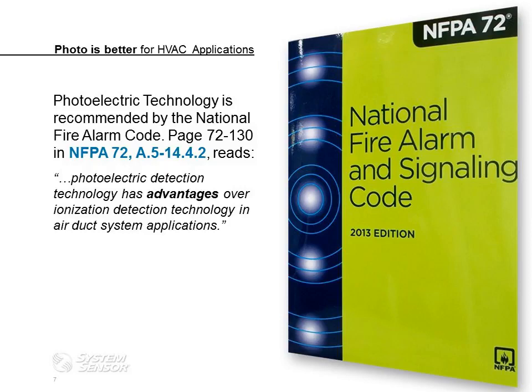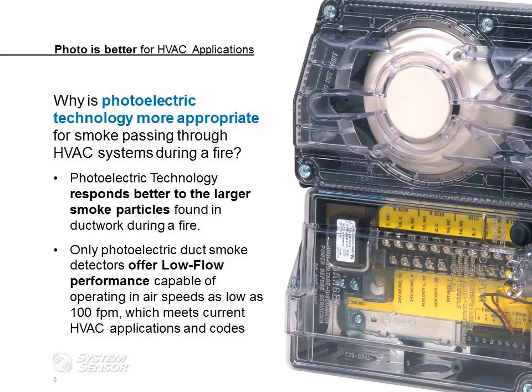NFPA 72 recommends the use of photoelectric detectors for HVAC applications. Photoelectric detection technology has advantages over ionization detection technology in air duct system applications. So what are those differences, and why is it appropriate to use photoelectric versus an ionization detector? Photoelectric technology responds better to the larger smoke particles found in ductwork during a fire. Another advantage is that only a photoelectric duct smoke detector offers low flow performance, capable of operating in air speeds as low as 100 feet per minute, which meets the current HVAC applications and codes.